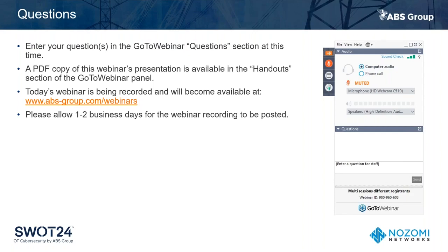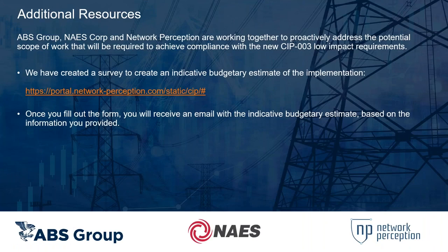Yeah. So some vendors have put in key switched firewalls and things like that, where there's a key switch that controls the power to the firewall. And some of those vendors have tied that into the panel alarm system so that the operator is aware when that is enabled. And that is a method. What I would say is, in the situations I've seen this, you typically still don't have access to that firewall, which means your monitoring of the connections to that firewall is at best hobbled.